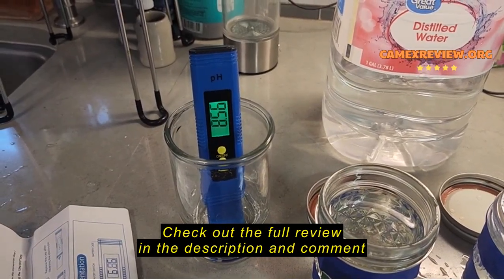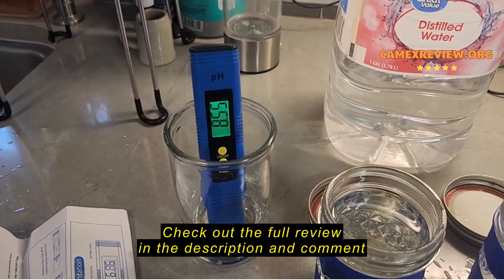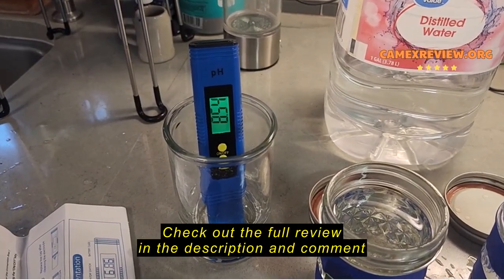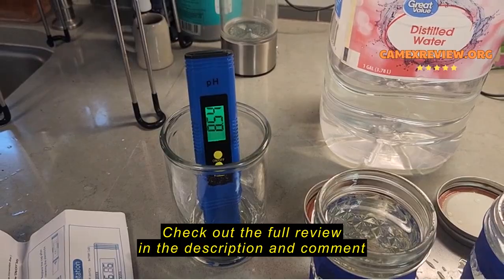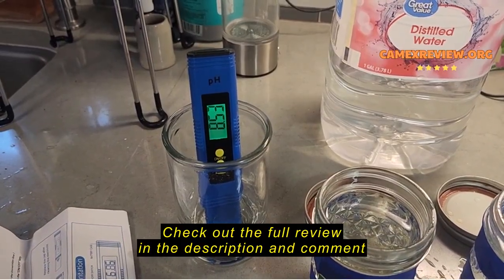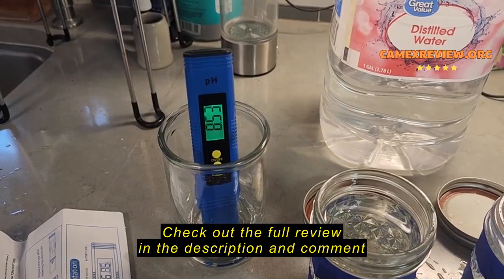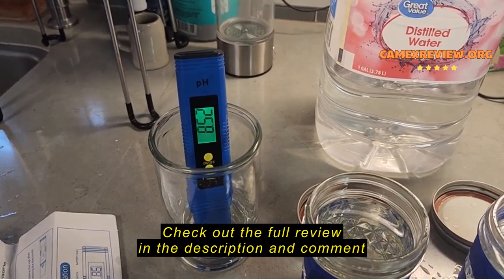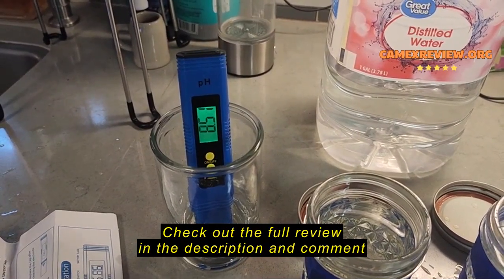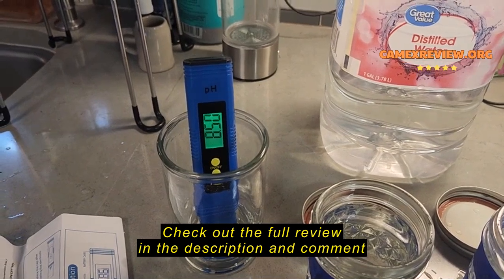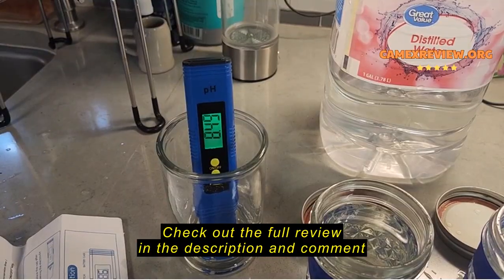And as you can see right now, I haven't used this one in a while, so I had to dip it in some distilled water to get the bulb rehydrated so it will give a more accurate reading. So distilled water should be 7.0, and as you can see, this is slowly counting down to there. And once it gets there, then we can do the calibration process.